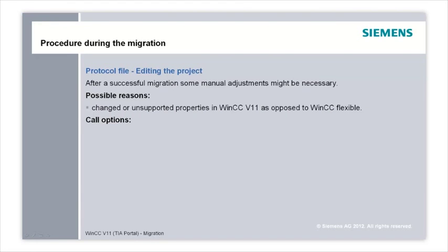After a successful migration, some manual adjustments might become necessary. Possible reasons are, for example, non-supported or changed object properties which are not realized in WinCC version 11 or realized differently than in WinCC flexible, stricter criteria for checking tag addresses or the length of object names in WinCC version 11. Object names in WinCC version 11 need to be unique throughout the project — a picture name, even if located in a subfolder, can only be used once in the project.